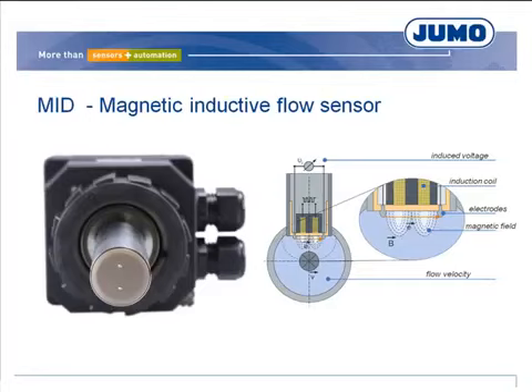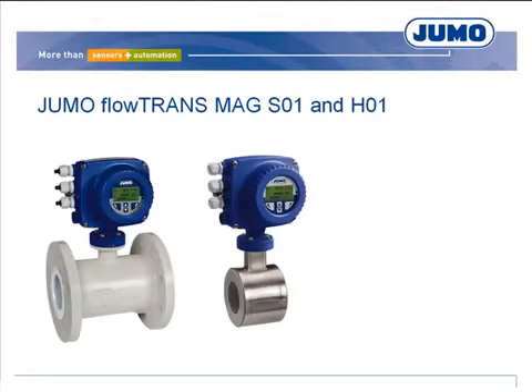flowing liquid. This voltage is tapped at two electrodes, which are also embedded in the sensor tip. So the sensor is wear and maintenance free. The temperature and pressure range is significantly larger compared to the paddle wheel sensor. However, the liquid must have a minimum conductivity of 20 microsiemens.